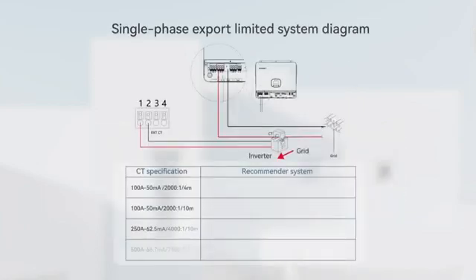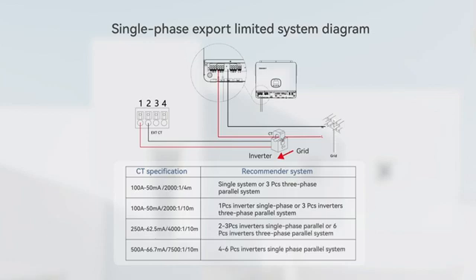CT is an optional accessory that needs to be purchased separately. For a single-phase system, only one CT needs to be connected to inverter number 1 and placed near the grid. Other inverters do not need an external CT. An entire single-phase parallel system only needs one external CT.